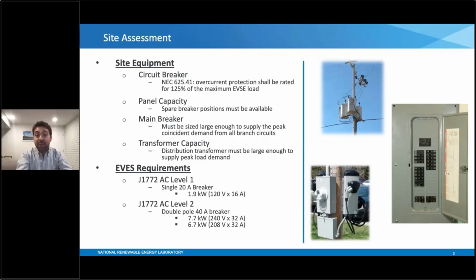In addition, you have at the top the main breaker rating, which protects all of these circuits below. That rating must be sized to meet the peak coincident demand of all your devices—what is the highest load that might be coming through your facility and demand at any given time?